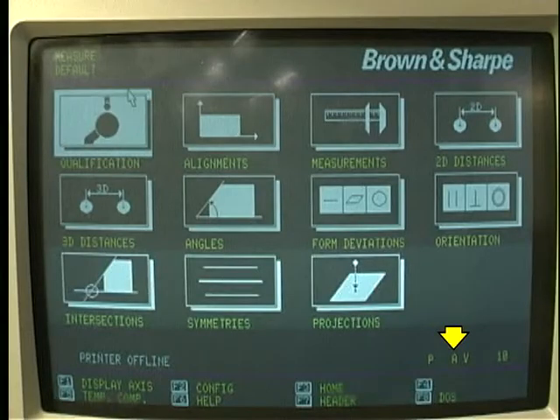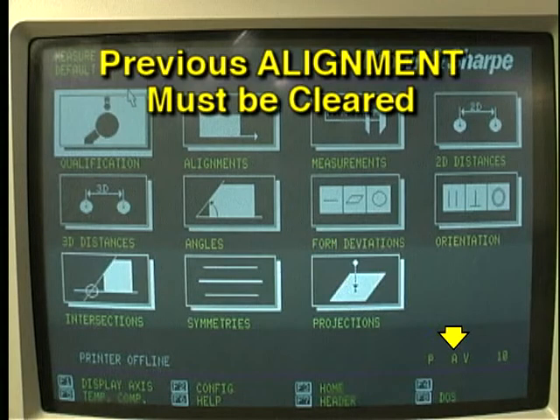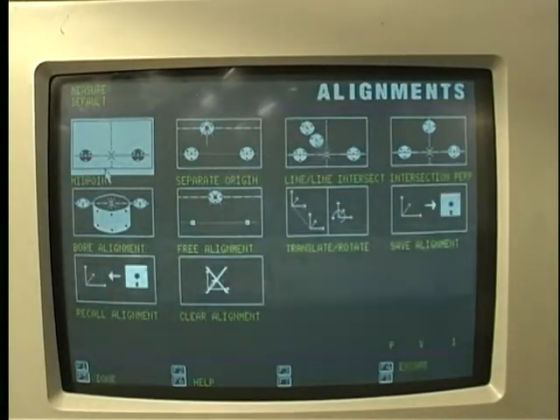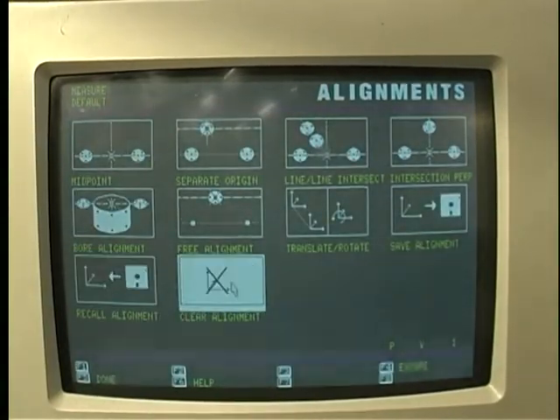The letter A on the status line means the coordinate grid of the CMM is already aligned to some point. This means a previous alignment is still active in the computer and must be removed. To remove the previous alignment, click on the alignments icon. Next, click on the clear alignment icon. The menu display returns and the letter A has disappeared from the status line.